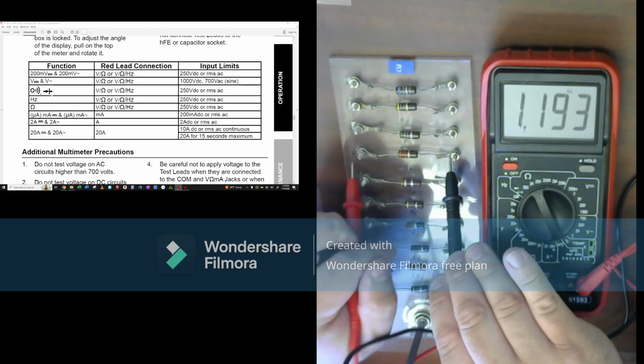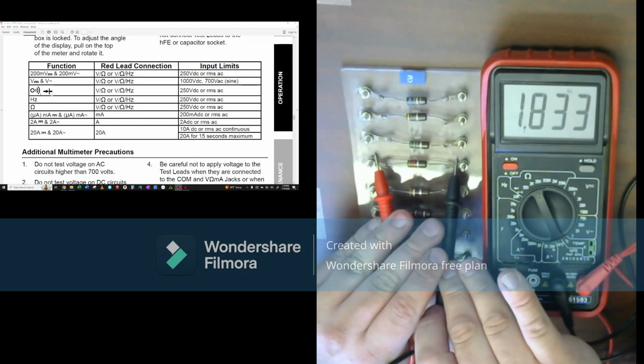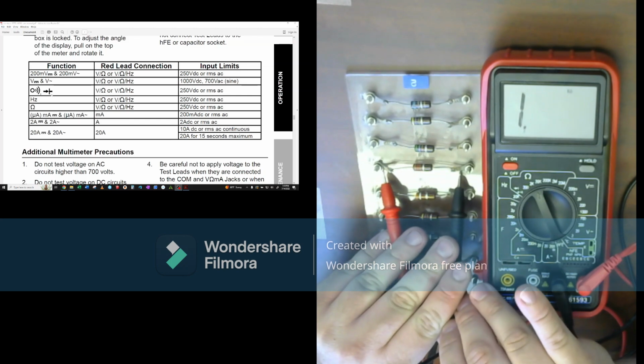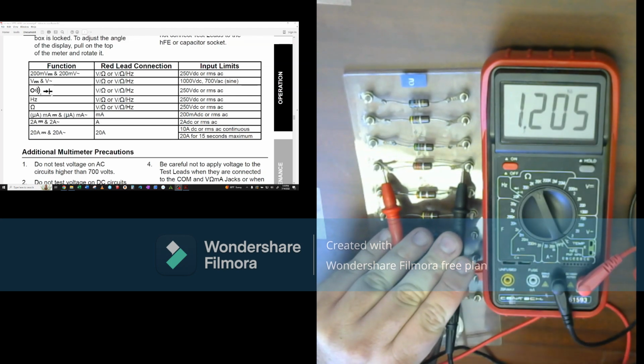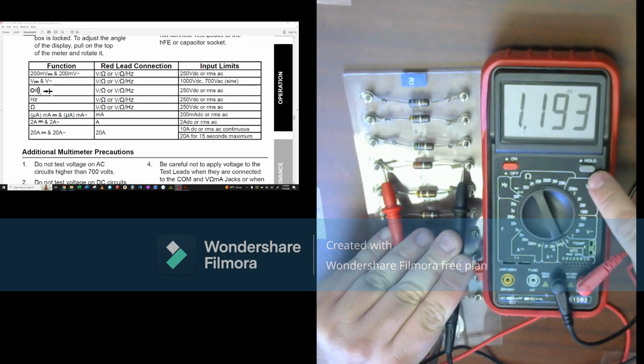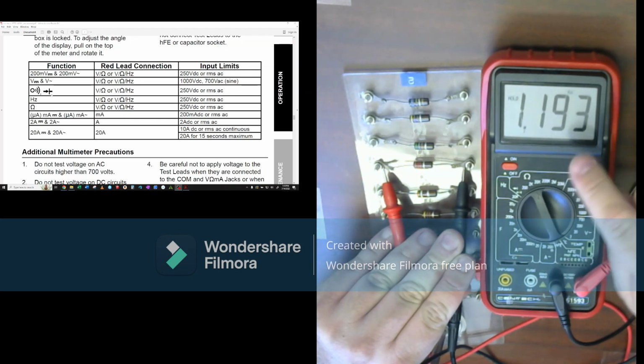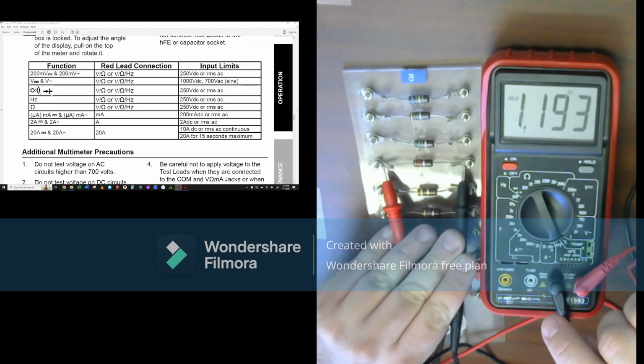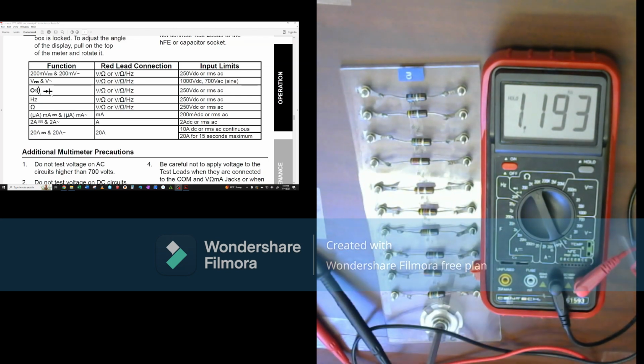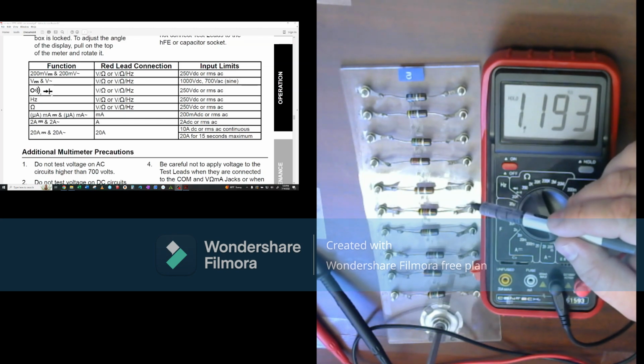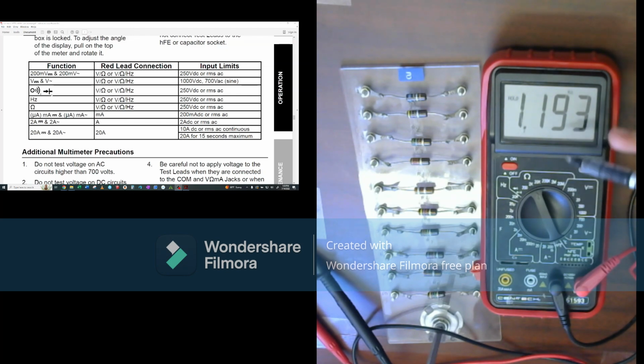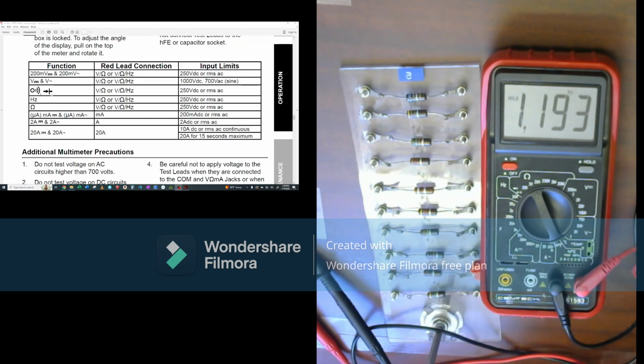One of the cool features is, if we hold the probes with one hand, we can measure our resistance and come up to this hold button. Pushing the hold button stores the value into memory, and now I can remove my probe, and it will remember what that value was even though it's not connected up. So when you hit hold, it holds the reading on the screen, so you can disconnect your hands, write it down, and do whatever you need to do safely. Then I can take that value and write it down as a 1.19 kilo ohm resistor, and move forward.